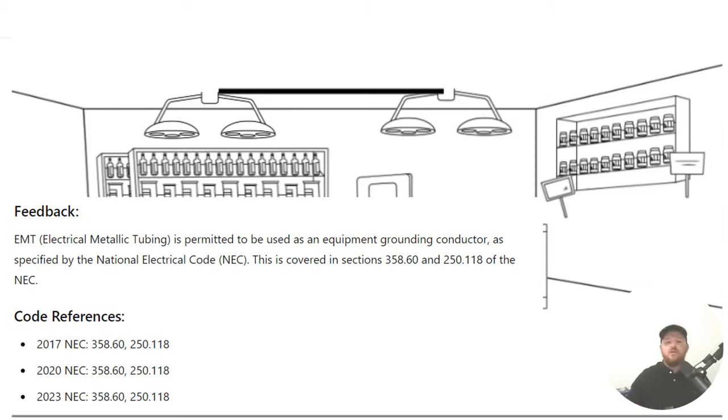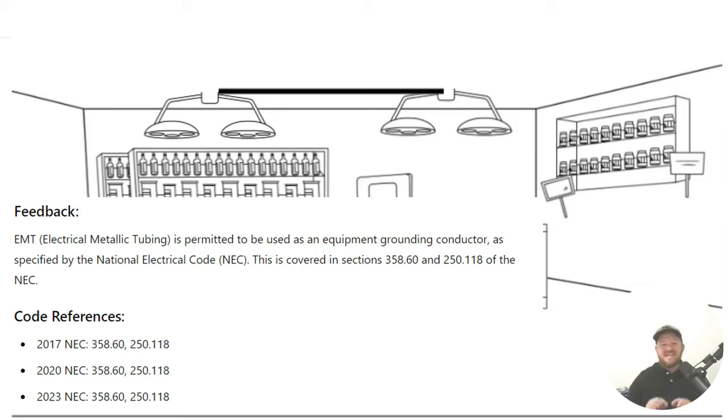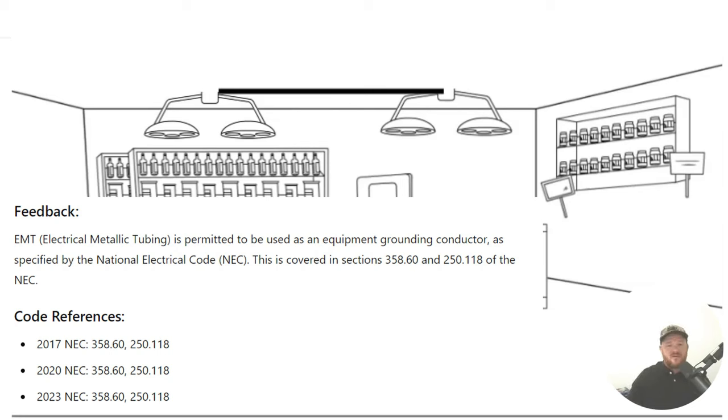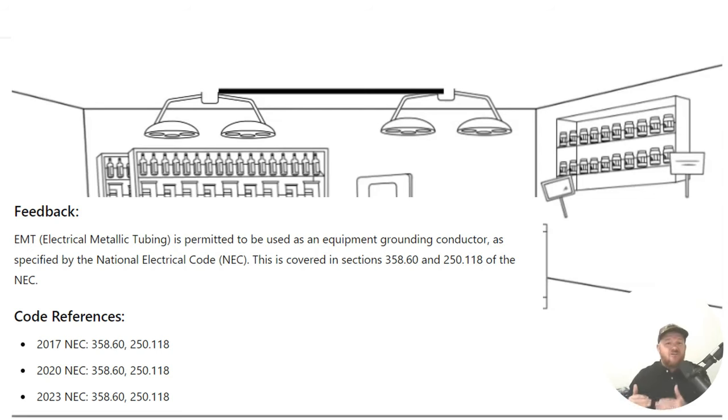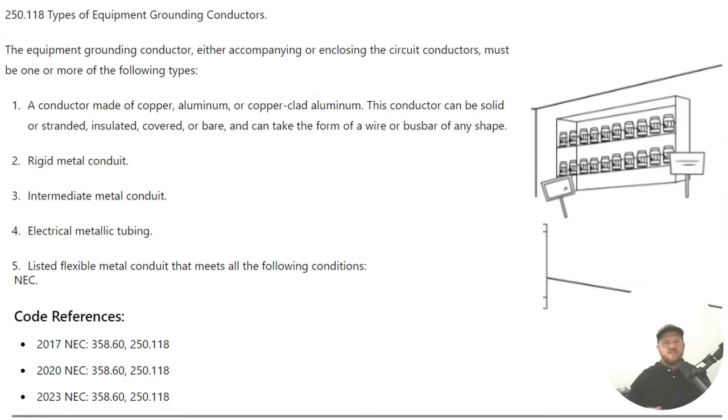Now, when we get over to 358.60, it is the NEC article all about EMT. If you want to learn everything you ever needed to know about installing it, you could go over to EMT. It'll tell you use is permitted, use is not permitted. It'll tell you about securing and supporting. And when you get to .60, it just says flat out EMT can be used as an equipment grounding conductor. And where this code really derives from is back in 250.118, where there is a very long laundry list of items that are allowed to be used as equipment grounding conductors.